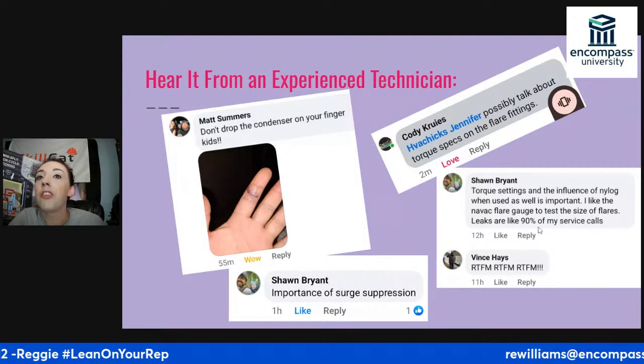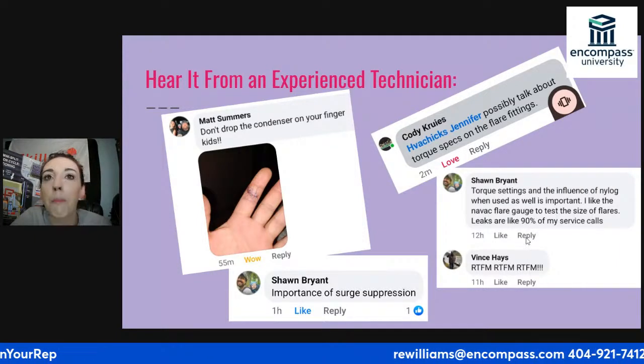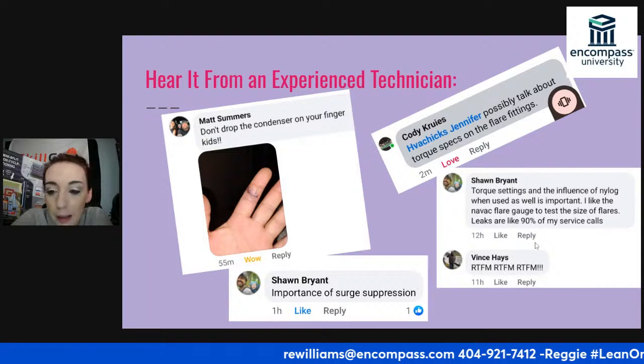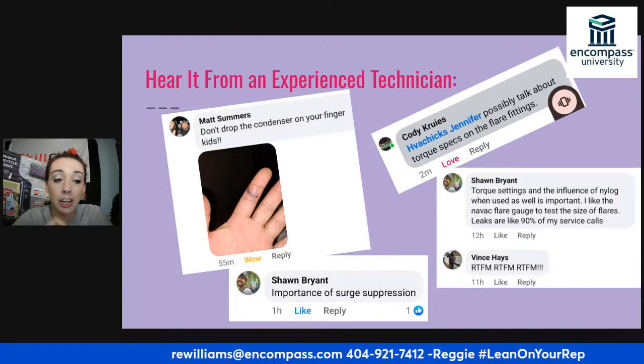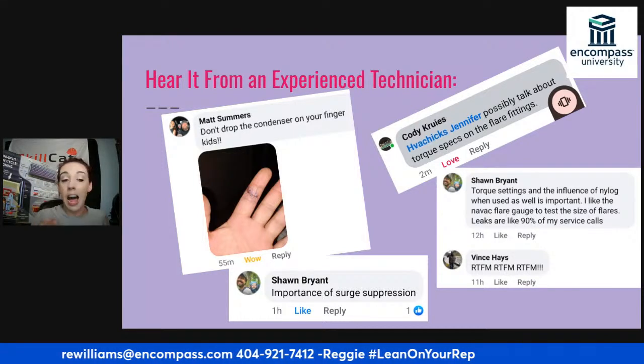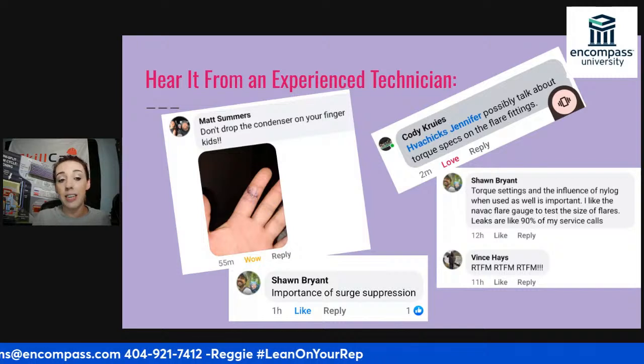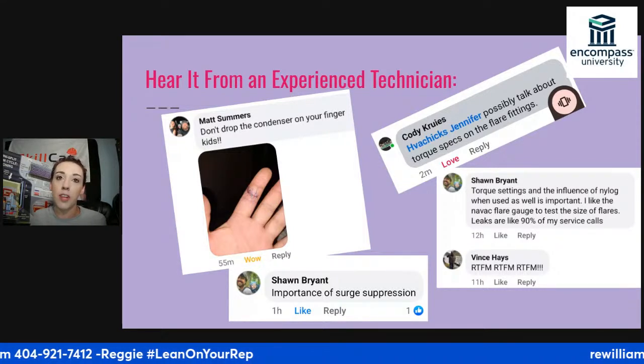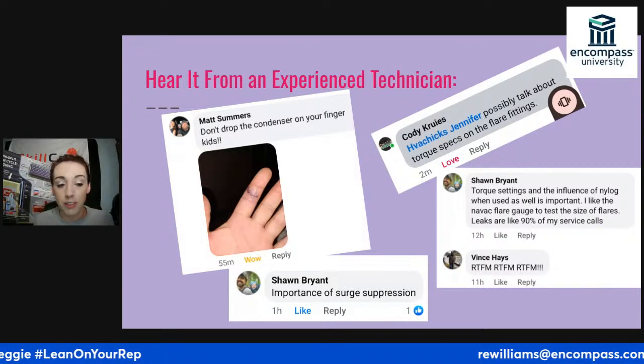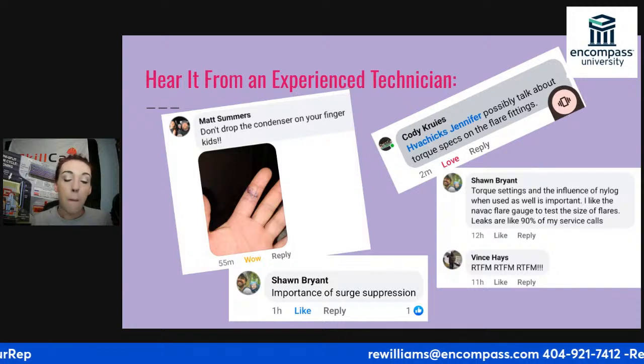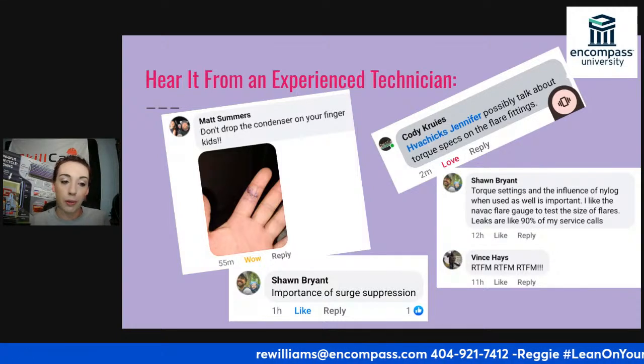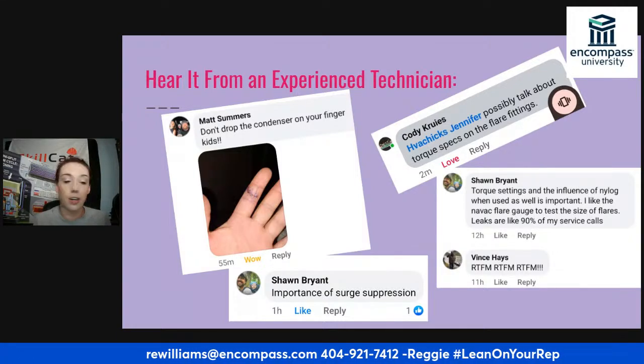Leaks are 90% of my service calls. This was important for me to add, when I'm talking about those factory flares which aren't really a flare, I'm not kidding. I'd say 90% is a good representation of how often we see somebody trusting a bad flare. With mini splits, the problem is typically low charge, and that's because these flares aren't done correctly.